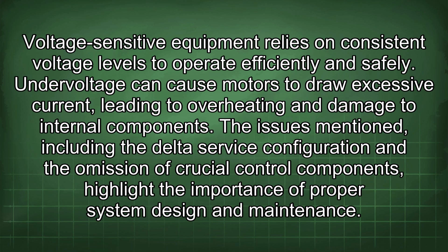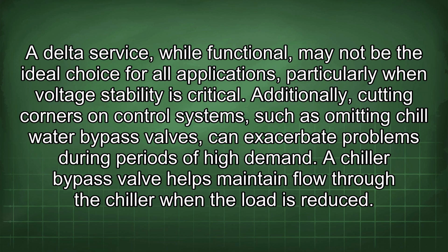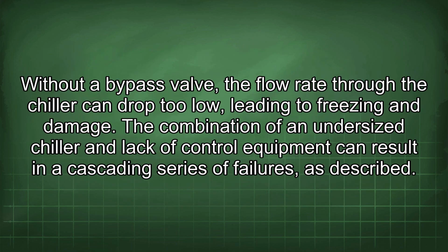The issues mentioned, including the delta service configuration and the omission of crucial control components, highlight the importance of proper system design and maintenance. A delta service, while functional, may not be the ideal choice for all applications, particularly when voltage stability is critical. Additionally, cutting corners on control systems, such as omitting chill water bypass valves, can exacerbate problems during periods of high demand. A chiller bypass valve helps maintain flow through the chiller when the load is reduced. Without a bypass valve, the flow rate through the chiller can drop too low, leading to freezing and damage. The combination of an undersized chiller and lack of control equipment can result in a cascading series of failures, as described.